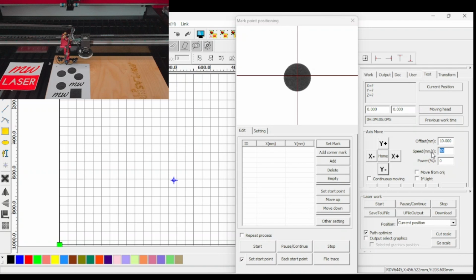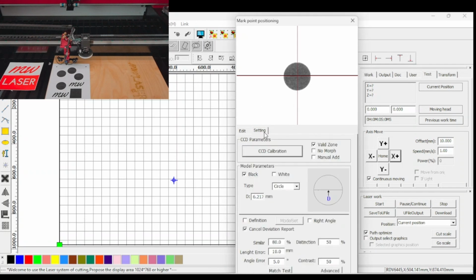So if you really want it to go slow, you can put in 1 millimeter a second and just move it 1 millimeter a second. The difference is now this still says an offset of 10. So if we want to have just continuous movement rather than an offset, we can go continuous movement, and it will just move a little bit at a time. So you can adjust using these buttons. Now, once you've got it close to center, then that's ready to go to the next step. So click on the setting button and enter the CCD calibration.